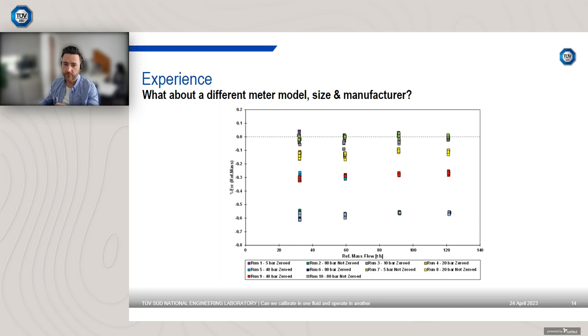I omitted the lowest flow rate. I did collect data at the lowest flow rate, but the zero effects are fairly significant, and it's not insofar as whether we zero or don't zero, it's just the fact that the zero can be quite temperamental. So there was quite a lot of scatter, so I've omitted it from this chart. I don't think it added a lot. But again, what we can see here is that there still is a pressure effect. So it's a different meter, it's a different model, it's a completely different size. You can see now we're up to 120 tons per hour, so nominally 30 to 120 tons per hour. Different manufacturer, but we're still seeing a clear pressure effect.